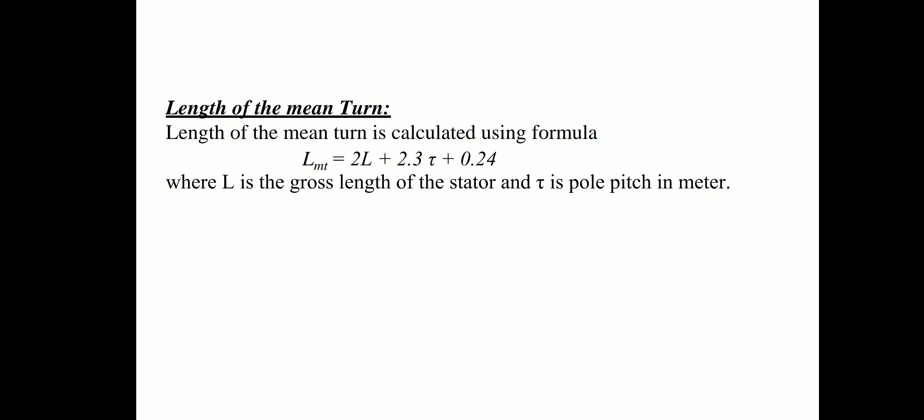The length of mean turn is calculated using: Lmt = 2L + 2.3τ + 0.24, where L is the gross length of the stator and τ is the pole pitch in meters.